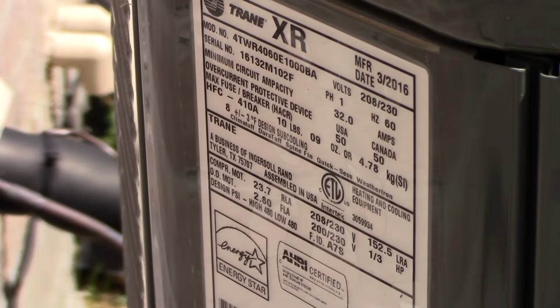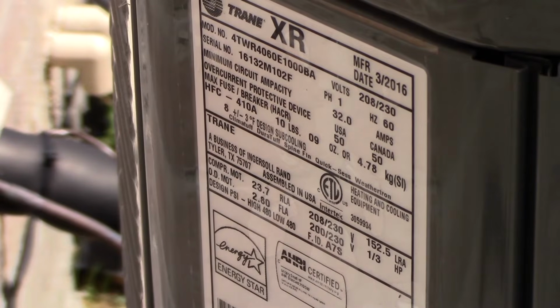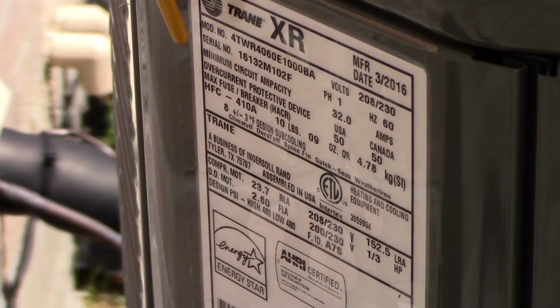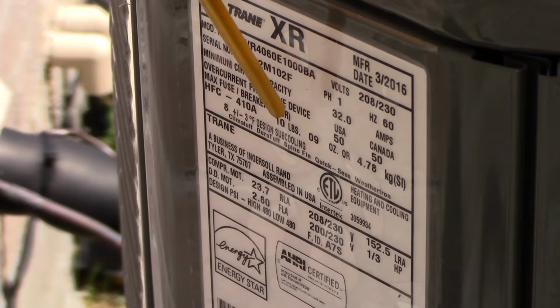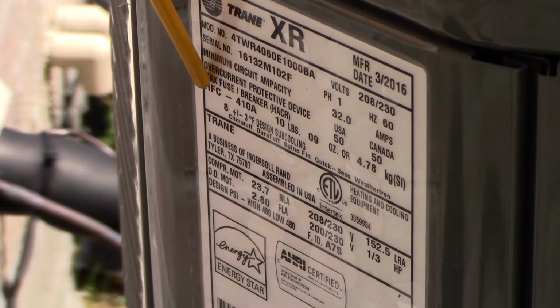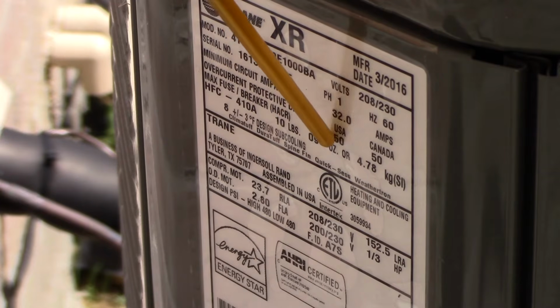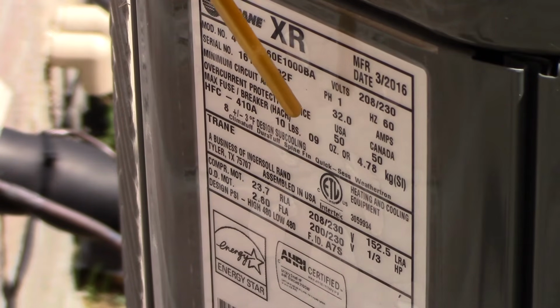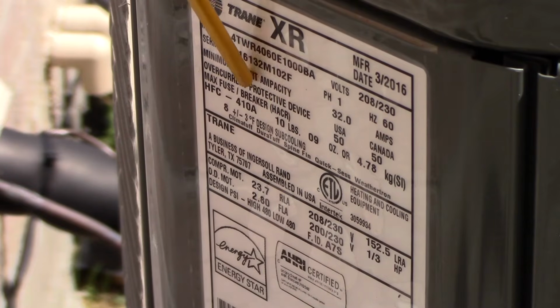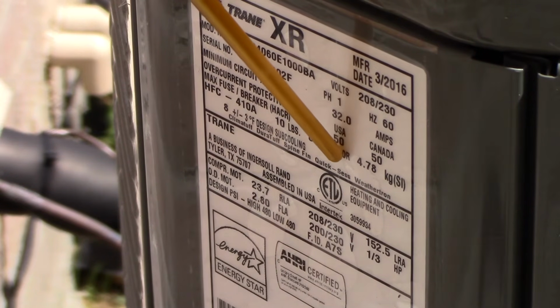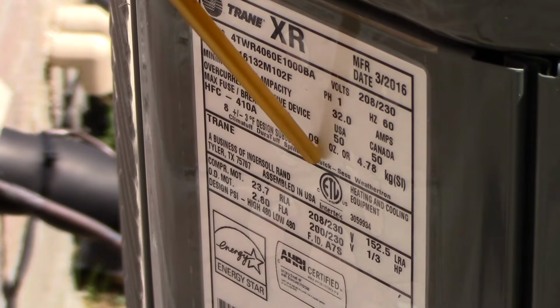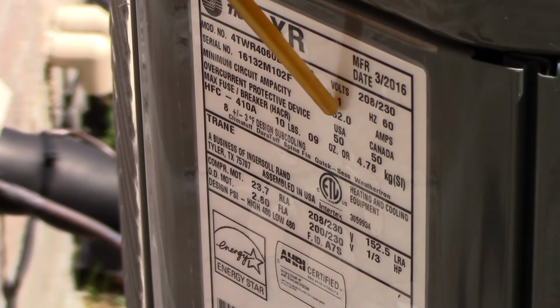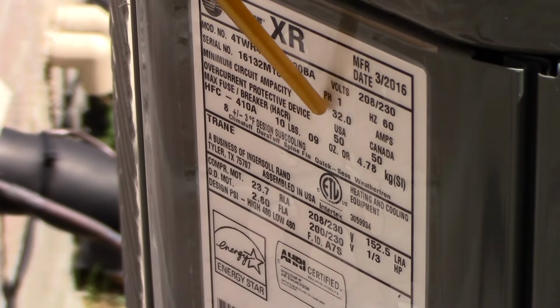Okay, remember earlier when we were talking about the outside unit and what the nameplate says? If you look at this nameplate here, you'll see that it says, right here, minimum circuit ampacity, and that's 32 amps. Then it says the maximum fuse or circuit breaker rating is 50 amperes. So you'll notice that I have a 32 amp wire and I have a 50 amp rated overcurrent protective device. So I can have a 50 amp breaker protecting a conductor that has at least an ampacity of 32 amps. Okay, then I have no problem here in this application.